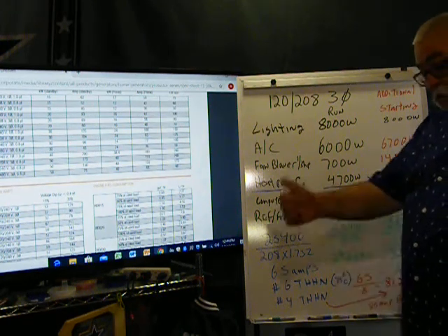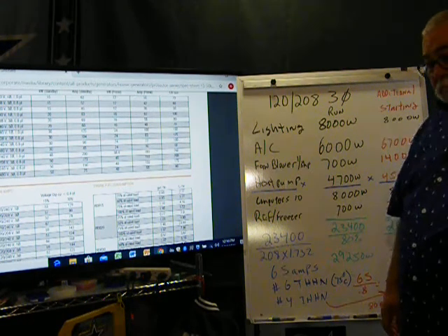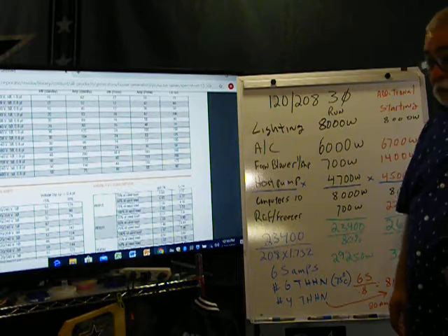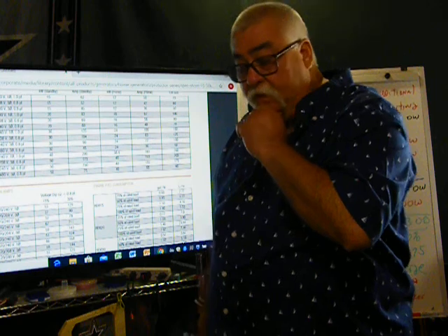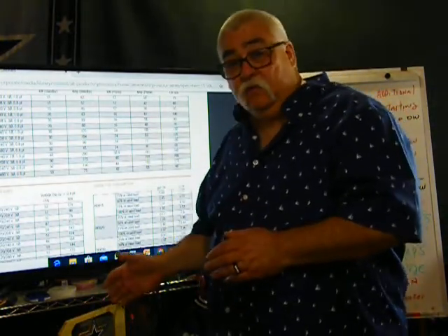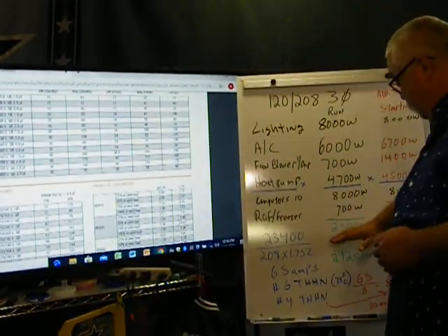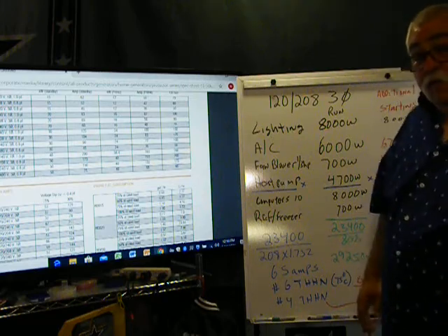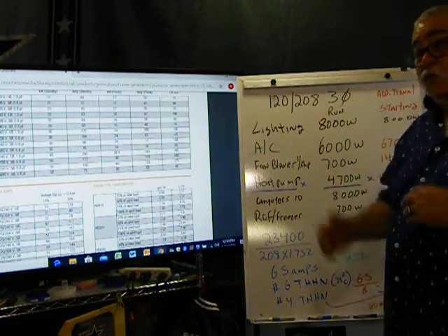They're usually 20, 22, 25, 30, 40, 50. I was reading on this sheet further up, and they were talking about making it larger than what you needed, 25% larger. So let's say if I needed 40,000 watts, then I would use a 50,000 watt generator, a 50 kW generator. So here I need 23, so maybe I want to go up to 25 to a 30. So I'm allowing for future expansion.